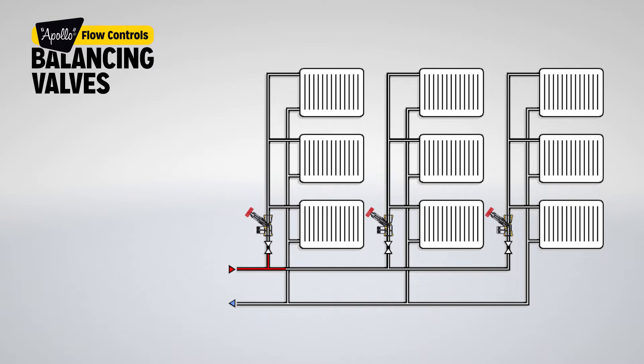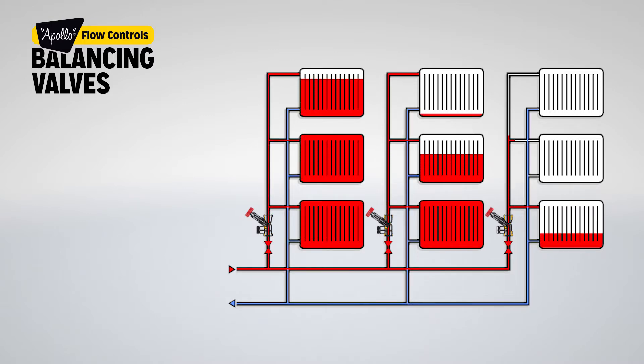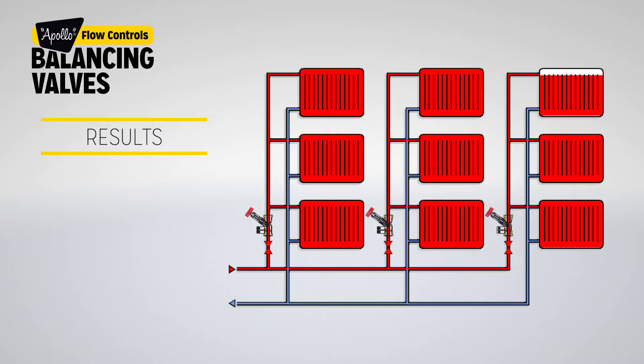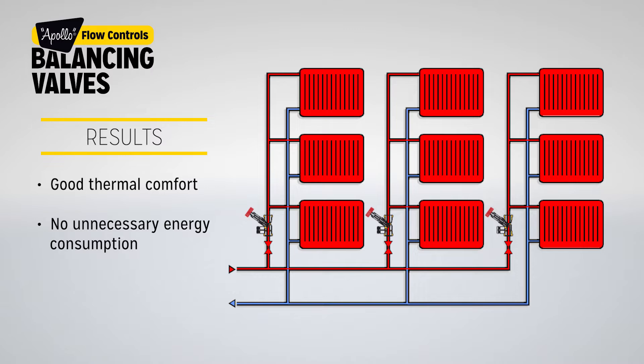When the system is balanced, water flow can be set to design requirements for all parts of the circuit. The results are good thermal comfort since all users receive the required energy, no unnecessary energy consumption, pumps operating with sufficient flow, and heat loss from the piping system especially in uninhabited areas such as basements, hallways, and staircases is minimized. In many cases, noise generation is also avoided.